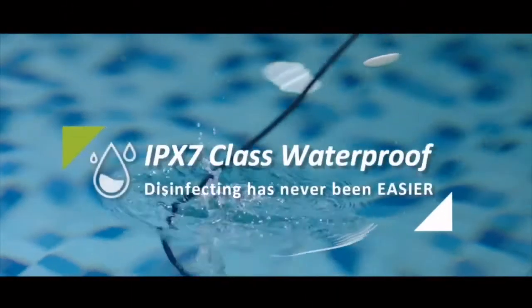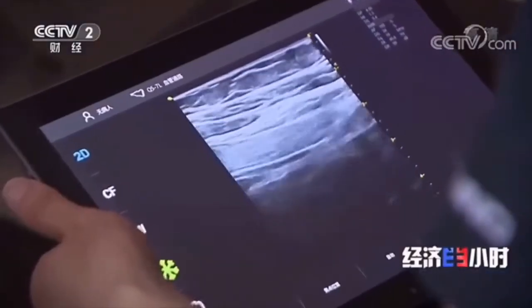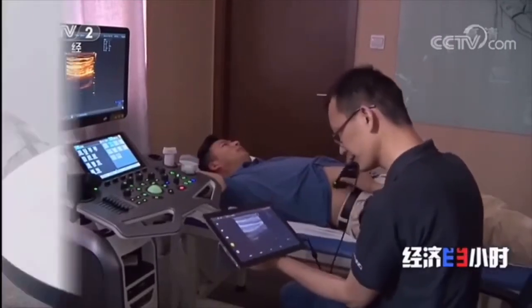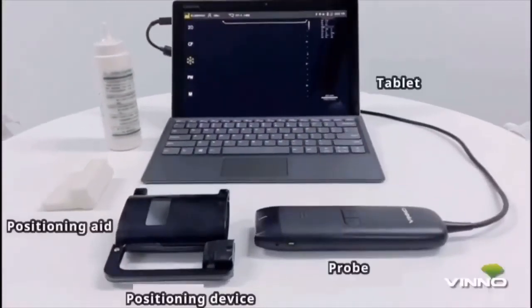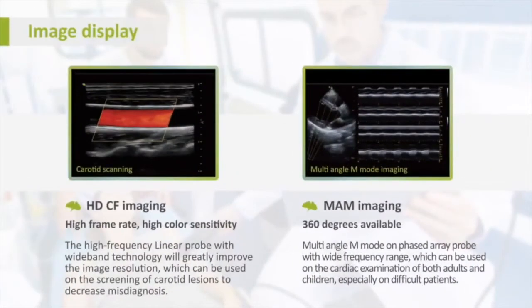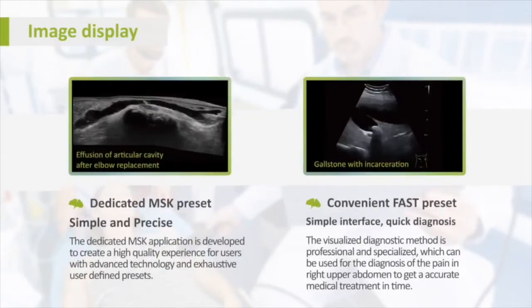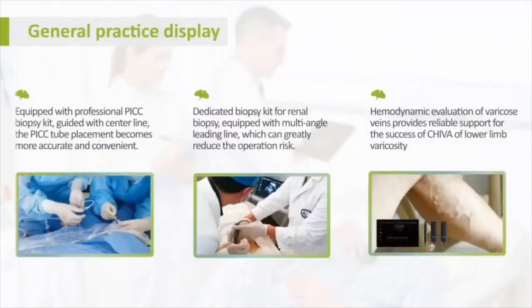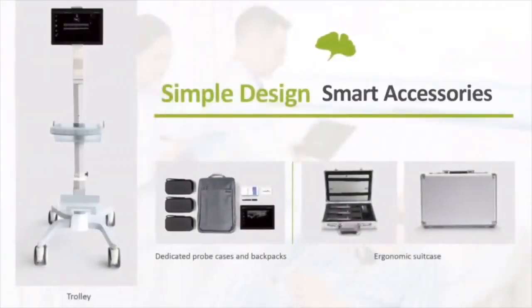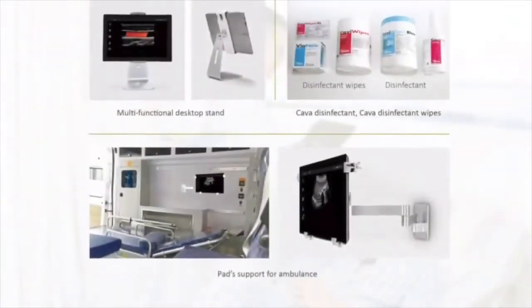Regarding the price, it's a one-time payment of €4,900 plus VAT for the whole package, which includes one probe that you can choose between linear, curved or phased array, plus one tablet with the software installed. Everything's included, not like Clarius, for example, that pulse wave Doppler was an additional $1,000. And contrary to the Butterfly IQ, there aren't any annual subscriptions. I think it's a very good price for what it offers. It costs less than other handheld devices and offers a wide range of advanced settings and imaging modes.